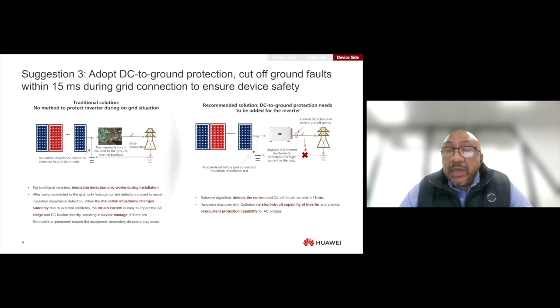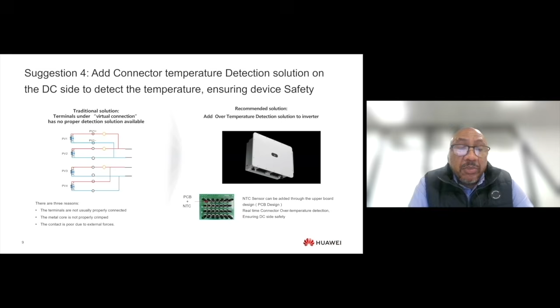Fourthly, we are looking at adding connector temperature detection on the DC side of the inverter, using a negative temperature coefficient sensor connected to the inverter that will easily pick up over-temperature events or conditions, primarily due to proper installation and correct wiring protocols and tools, where terminals may not be properly connected or crimped.